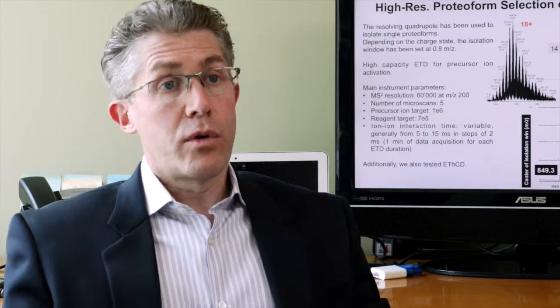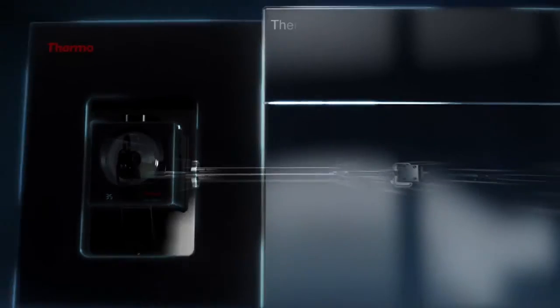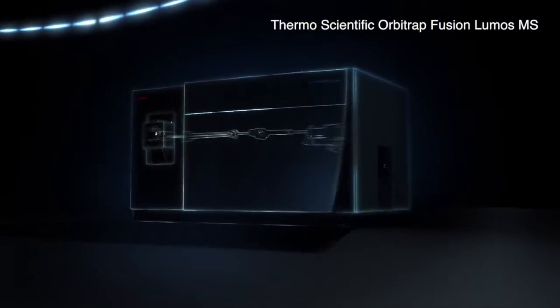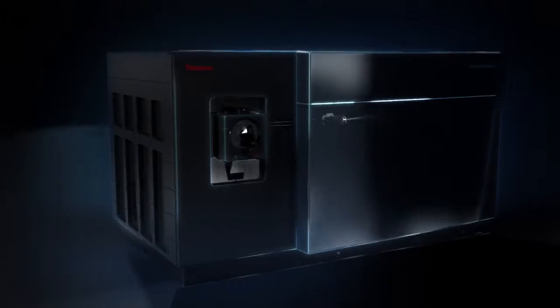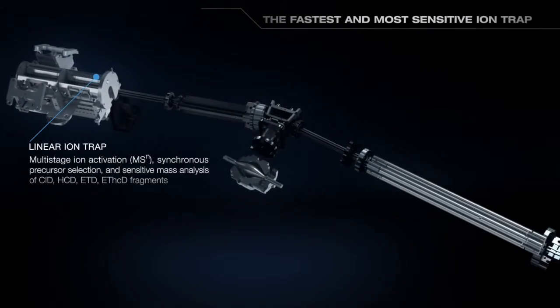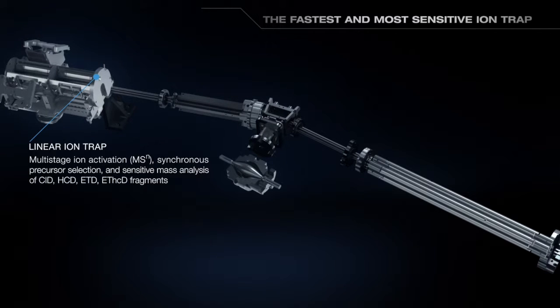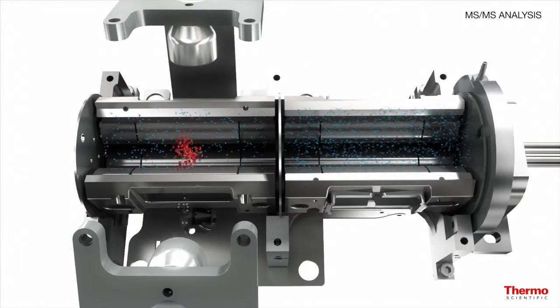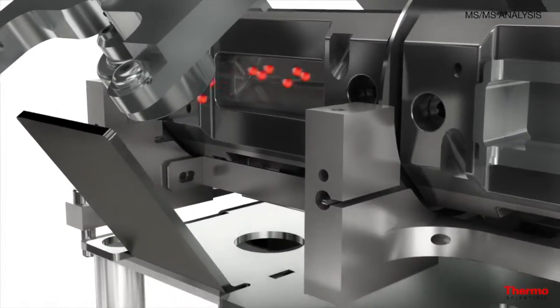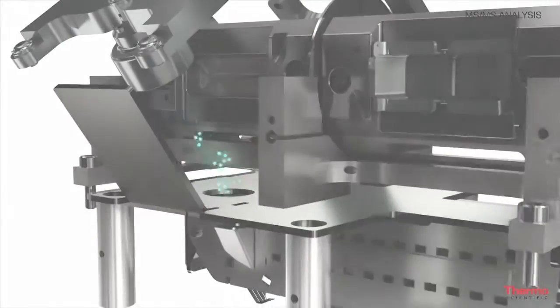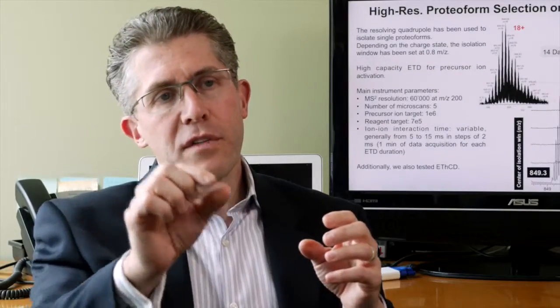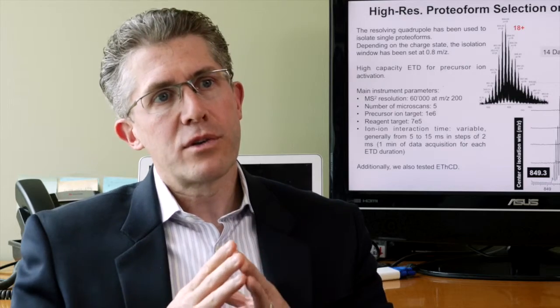In the Orbitrap Fusion Lumos we have a platform that really contributes and increases the power of all three of the things that we try to do well. On the quantitation front, you have the ion trap back end which is critical with its AGC automatic gain control functions to make sure that you're counting ions well. On the identification part, we want to pluck proteoforms specifically with narrow bandwidth isolation and that's endowed upon the instrument with the front end quadrupole.